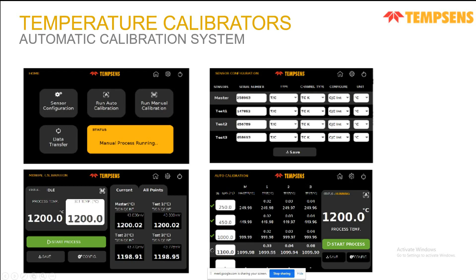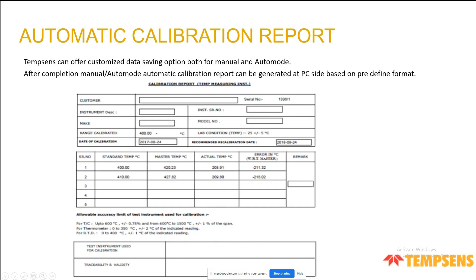You can also do a manual one, in which you can see something like this, and you can record the reading manually. This is the initial screen. You can put in the serial number and the type of thermocouple, so it is suitable for all different kinds of thermocouples and RTDs. Finally, you can get a calibration report like this one. So you can get the temperature at which you had set, the master and actual temperature, and the deviations.